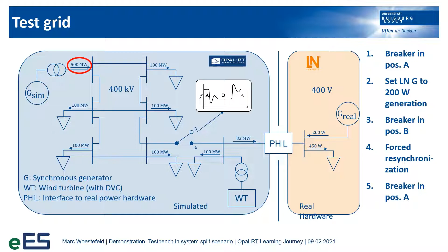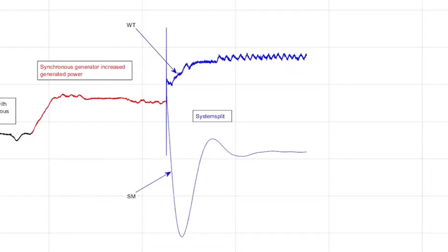On the other hand, the wind turbine doesn't have to provide the power anymore for the simulated grid, so the frequency will rise. In this case here, the wind turbine has a grid-forming control, visible in the spikes right at the split moment. There are angular steps, thus frequency deviations, which will result in adjustment of the sudden change of grid impedance. With grid-following control, the frequency either would not be caught, so the system becomes unstable, or the absolute frequency deviation would rise much higher.